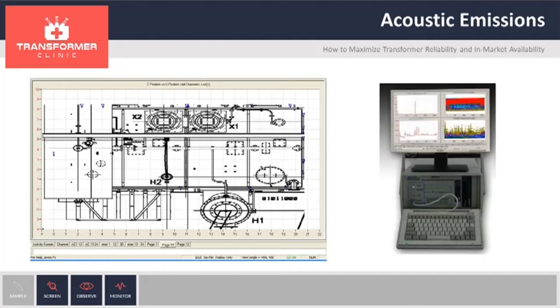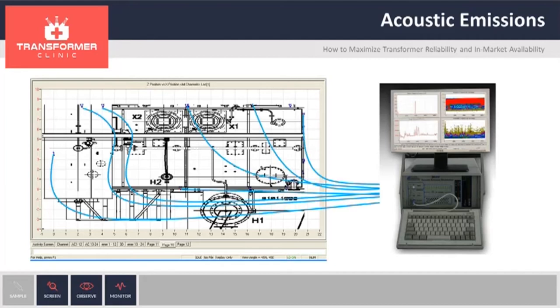The sensors are installed with magnets on the four walls of the transformer, always working within the same distance for the electric clearances. We have an acoustic emission instrument with cables from the sensor to the instrument. While listening to whatever is happening on the unit, if there is an active fault on the transformer, the fault is going to produce a sound. The sound travels from wherever it is located to the tank wall. As soon as the pressure wave hits the tank wall, we see the electrical signal produced by that fault. We know the position of the sensors, the size of the transformer, and the velocity of propagation of the sound, and with that information we can triangulate and locate the fault.